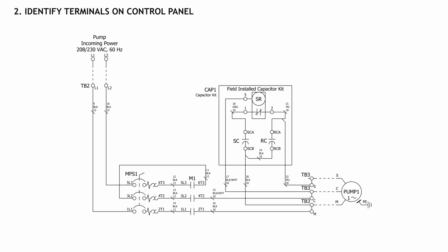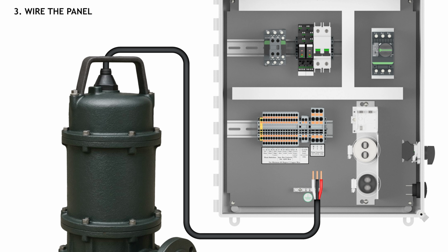Step 2. Identify the control panel pump terminals for connection of the common, main, and start windings. View the control panel's schematic either pasted on the inside door or provided in paper form. Find the pump electrical symbol that will have dashed lines connected to terminal blocks. These terminal blocks should be marked for common, main, and start windings. If only colors are shown, simply follow the wire from the pump terminal block, and as previously mentioned, the wire that goes to motor start relay terminal 5 is the common winding, while the wire connecting to motor start relay terminal 2 is the start winding, and the main winding is not connected to any terminal of the motor start relay.